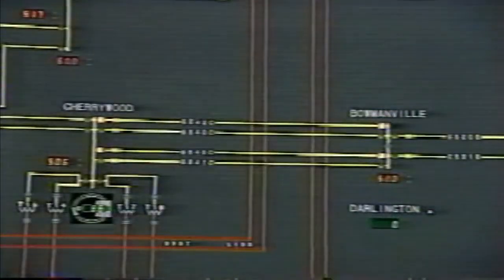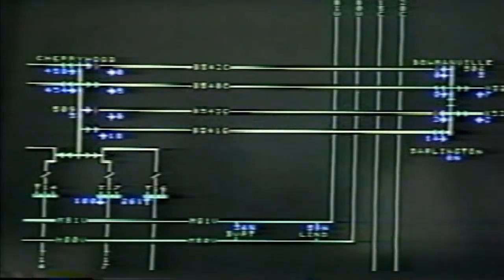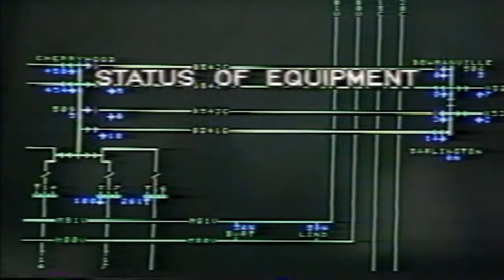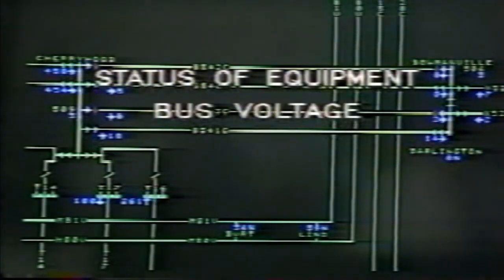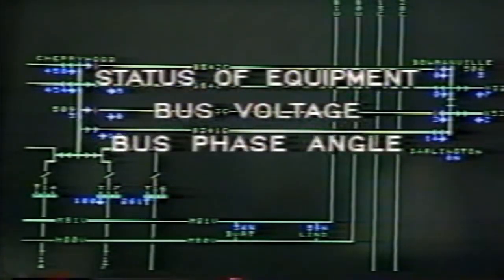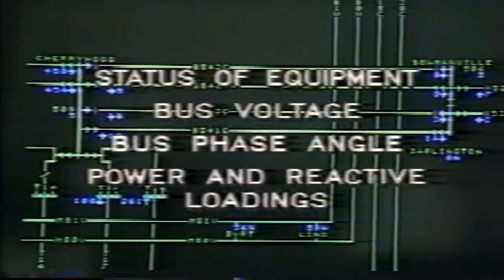Quite often, line loadings are indicated on a large wall map, but more detailed information is available on the CRT screens. Typically, for any particular bus, the operator can view the status of equipment, that is, breakers closed or open, bus voltage, bus phase angle in comparison with the system reference bus, power and reactive loadings, including direction on connected equipment such as generator, lines, etc.